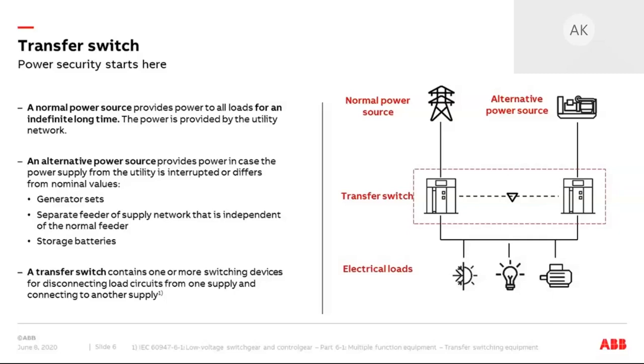In order to guarantee power continuity, these loads usually have more than one source of power. In addition to the normal power source, which provides power for an indefinitely long time, these loads have an alternative power source that provides energy in case power supply from the normal source is interrupted or differs from nominal values. Normal power source usually comes from the utility, while the alternative power source can be generator sets, a separate feed or supply network, or an energy storage system. This brings us to the definition of a transfer switch: equipment containing one or more switching devices for disconnecting load circuits from one supply and connecting to another.